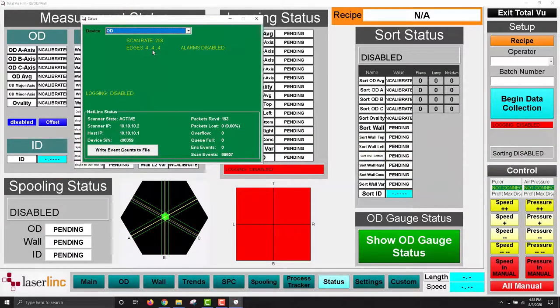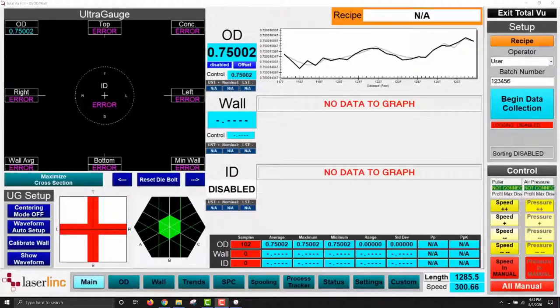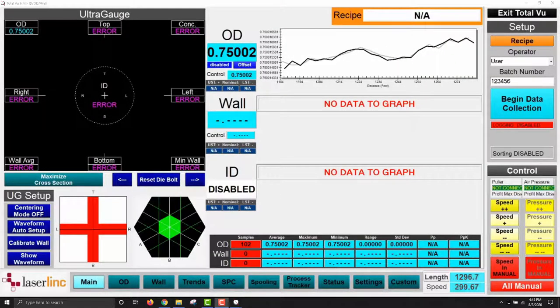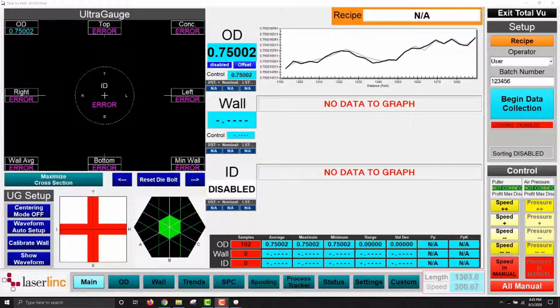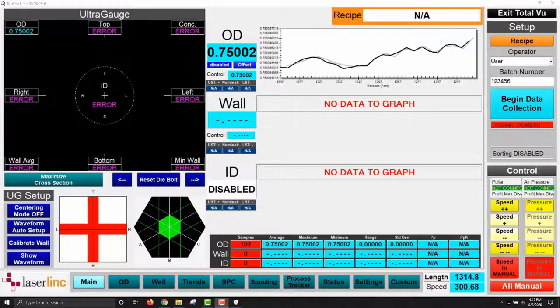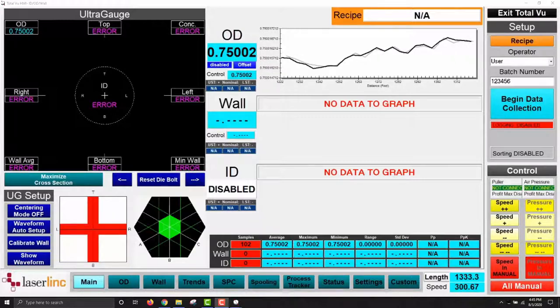Close out of the general status window and view the main display. Verify that the encoder signal is properly coming through by checking that the length value is counting as the encoder is ticking. If the length value is updating successfully, speed value should also be updating.